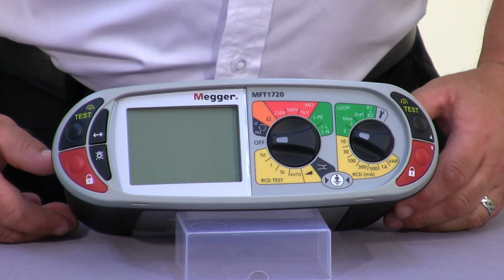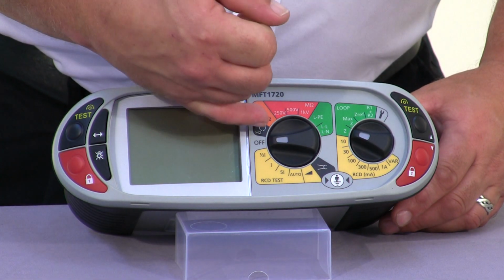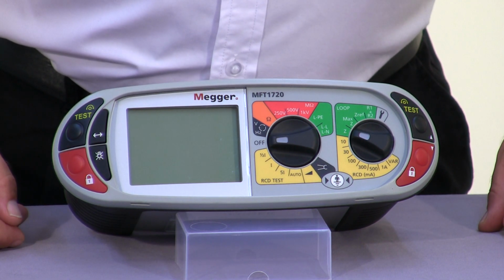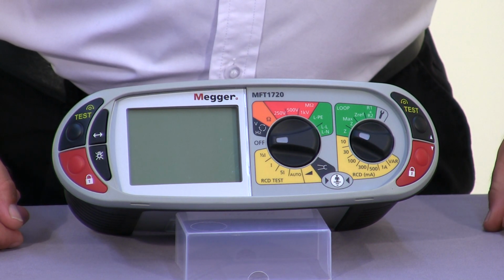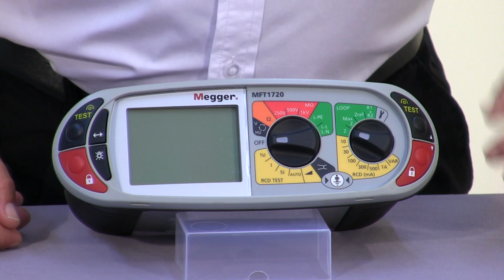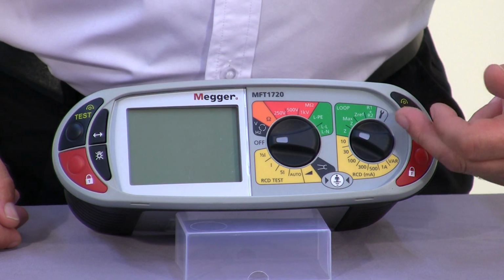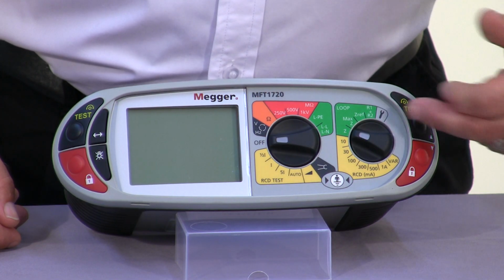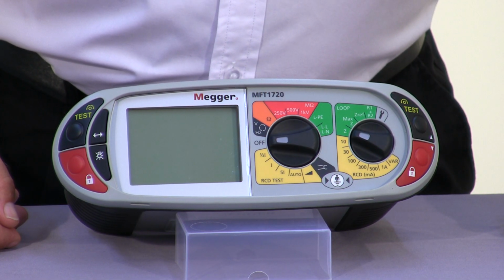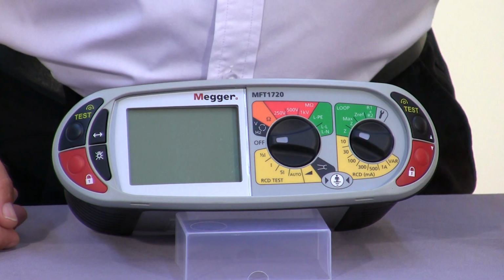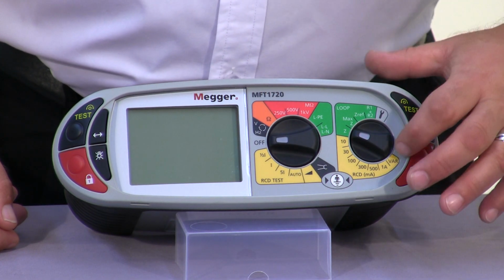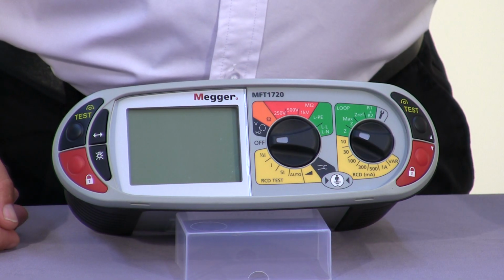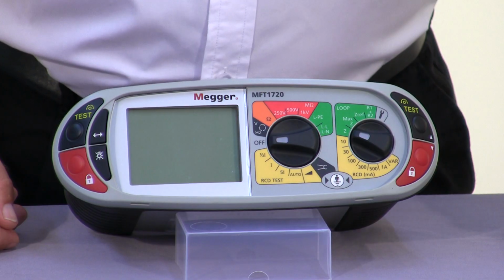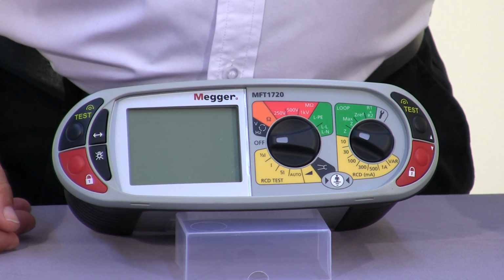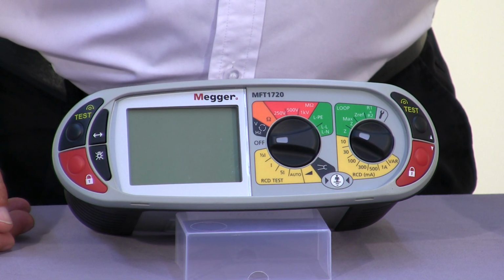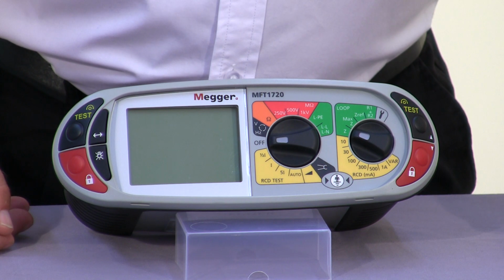Moving on to the MFT1720, we now have incorporated a full phase rotation meter. On the insulation range, we've added the 1kV test facility. And on the loop impedance range, there's some additional features, namely the ZMAX facility and a calculated R1, R2. The RCD tester now incorporates an auto RCD function, as well as the facility for testing variable RCDs. The CT input, using the optional CT, will allow you to take either measurements for diversity or for earth leakage measurement.